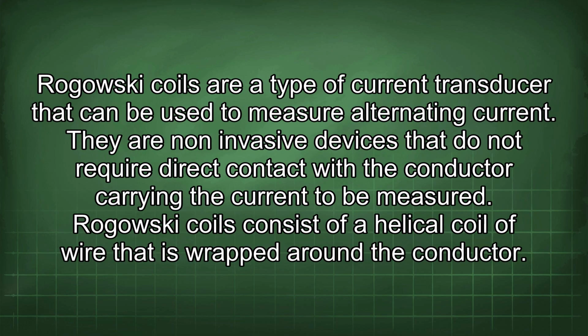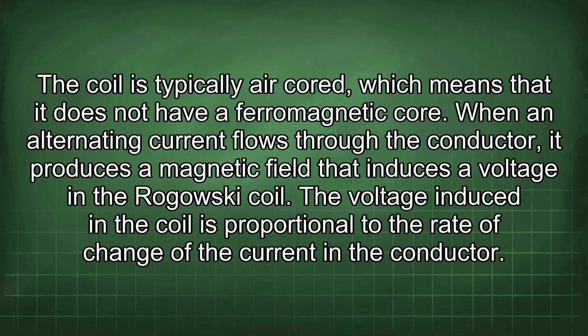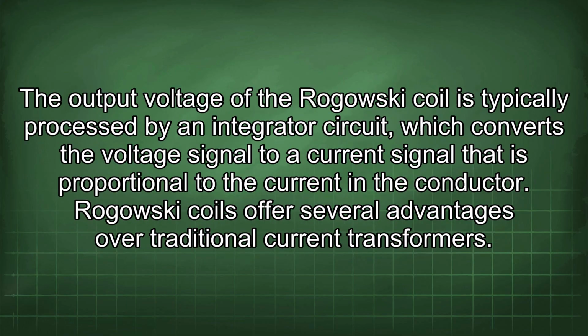Rogowski coils are a type of current transducer that can be used to measure alternating current. They are non-invasive devices that do not require direct contact with the conductor carrying the current to be measured. Rogowski coils consist of a helical coil of wire that is wrapped around the conductor. The coil is typically air-cored, which means that it does not have a ferromagnetic core. When an alternating current flows through the conductor, it produces a magnetic field that induces a voltage in the Rogowski coil. The voltage induced in the coil is proportional to the rate of change of the current in the conductor. The output voltage of the Rogowski coil is typically processed by an integrator circuit, which converts the voltage signal to a current signal that is proportional to the current in the conductor.